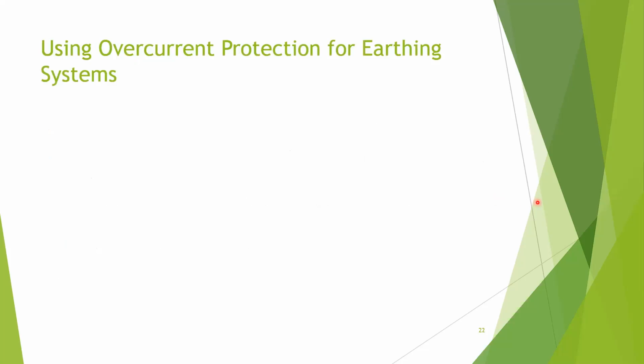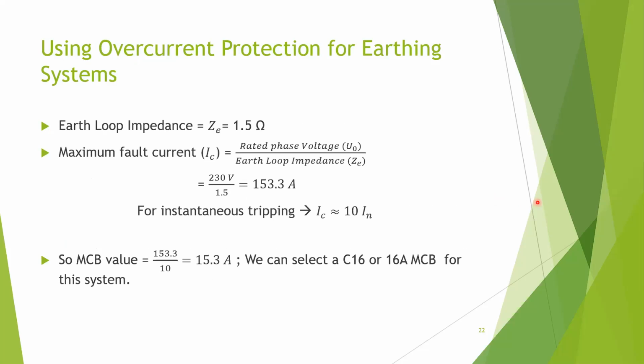And so we can also do calculations to design overcurrent protection for TNC systems. In TNC systems our loop impedance is low. I earlier said in TT systems loop impedance is around 10 ohms. In TN systems it is 1.5, probably less than that. So if earth loop impedance is 1.5, we can calculate the current in a fault by dividing the rated voltage by earth loop impedance. It will be 153 amperes if the earth loop impedance is 1.5.